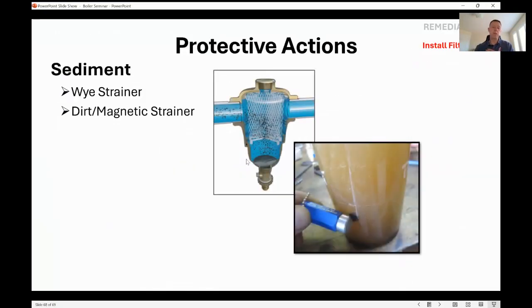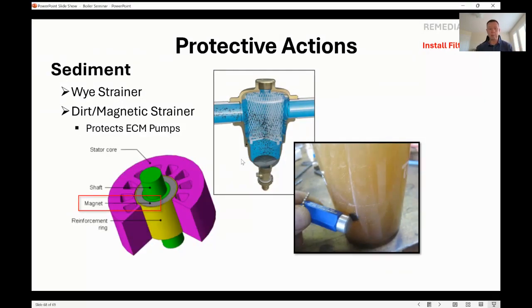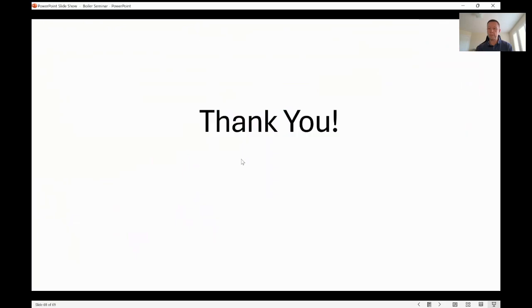And personally, I always recommend Y strainers and dirt magnetic separators, because more and more magnetite is a problem. It can cause issues with the boiler, especially in a higher mass boiler where it's less turbulent in there. Sometimes the sediment can get lodged into a corner by the fire tube, create a galvanic cell, and start corroding that heat exchanger. And of course, it can cause problems with your ECM pumps as well.